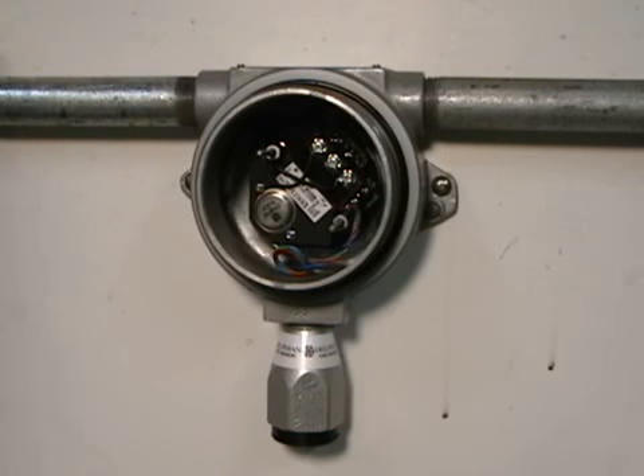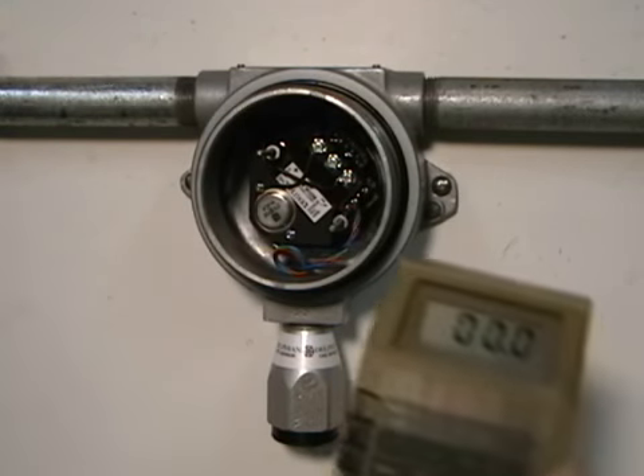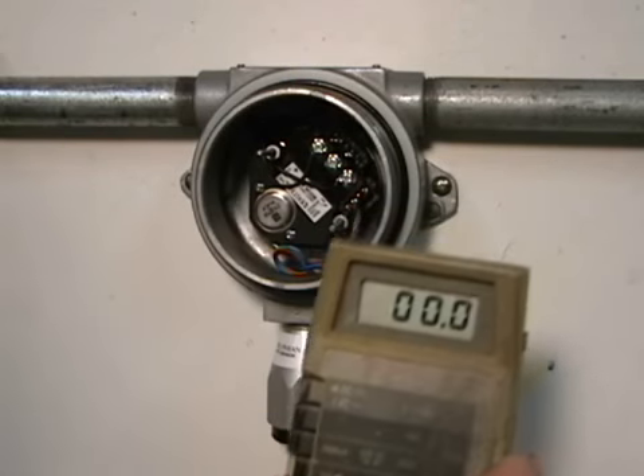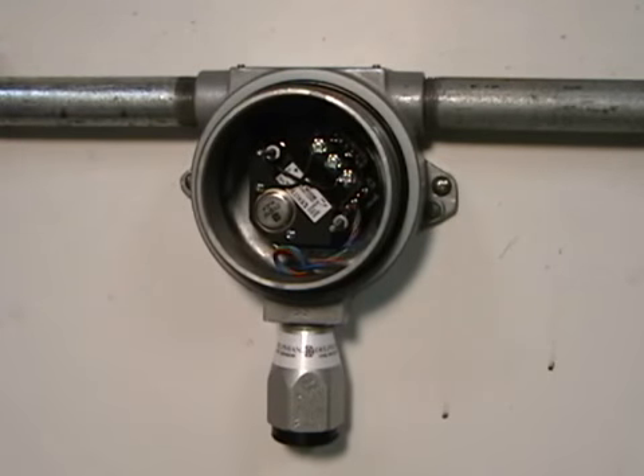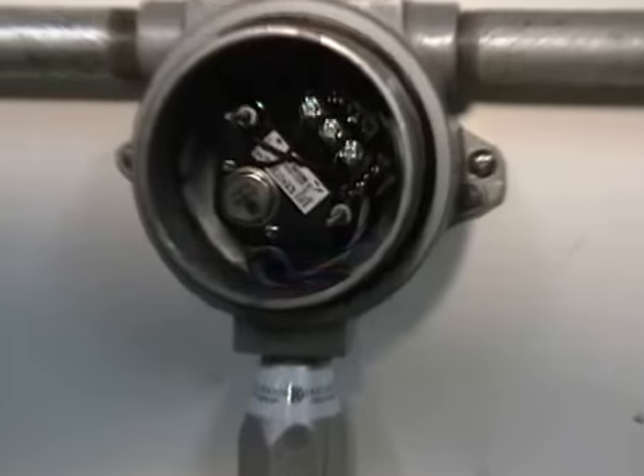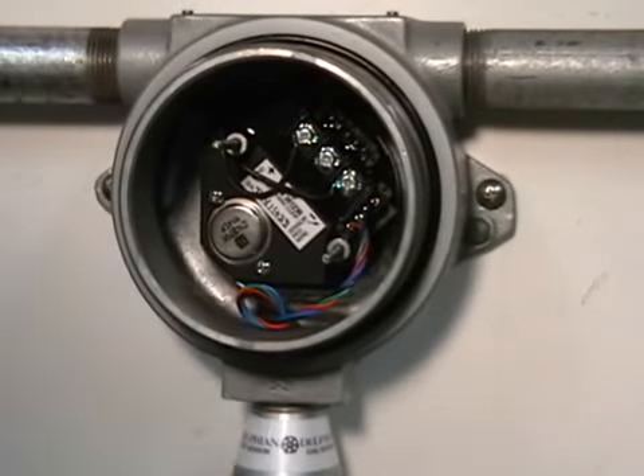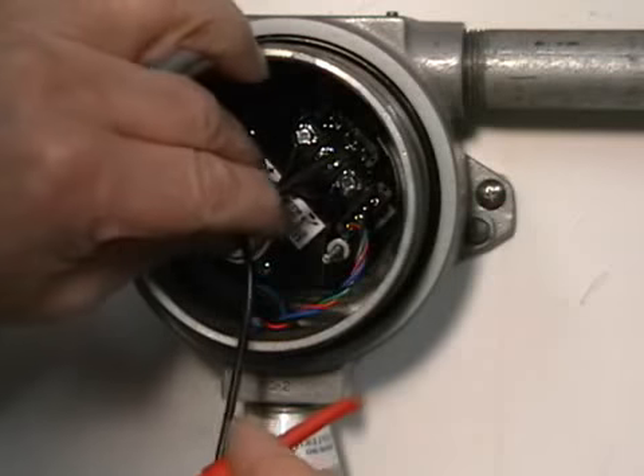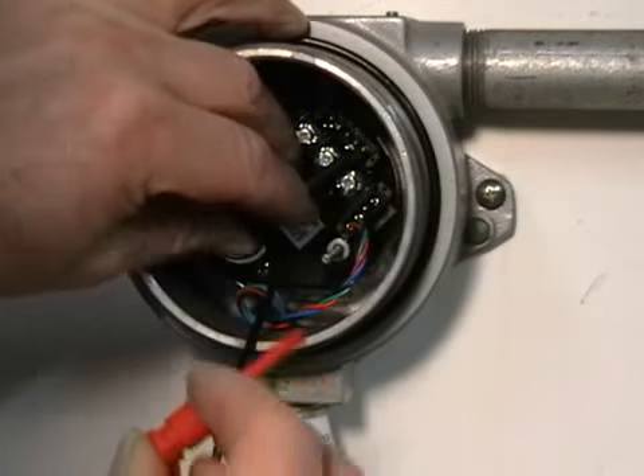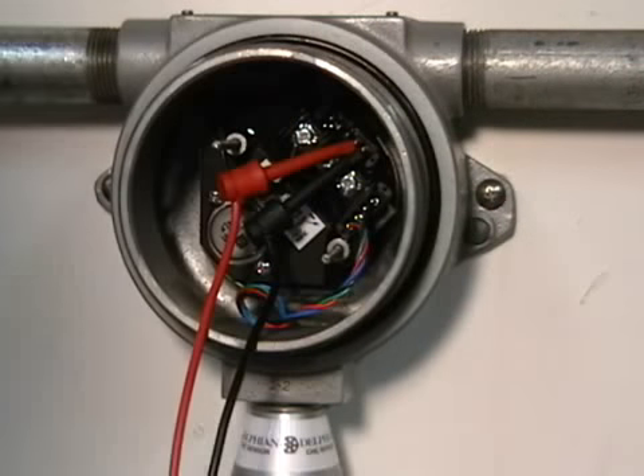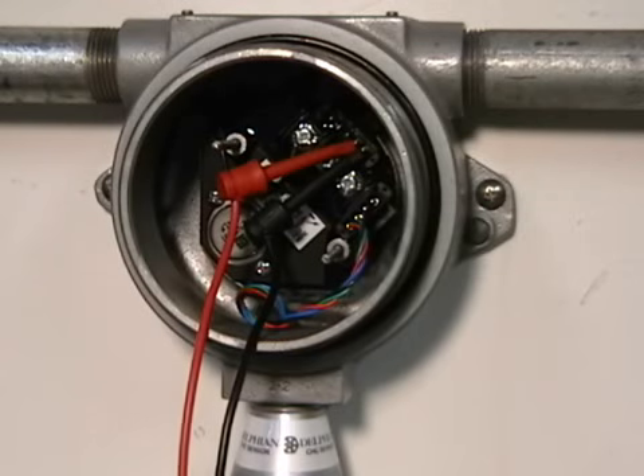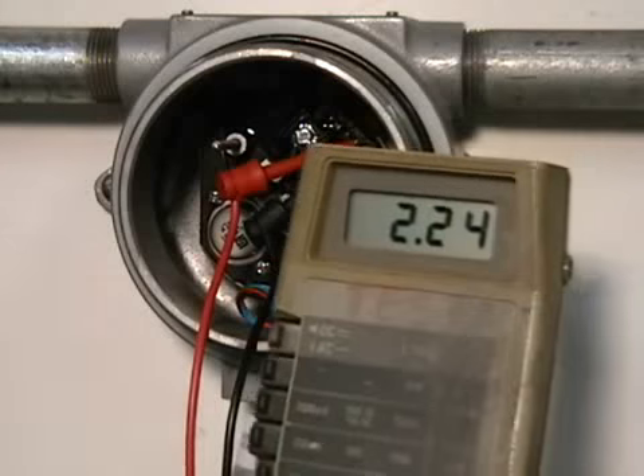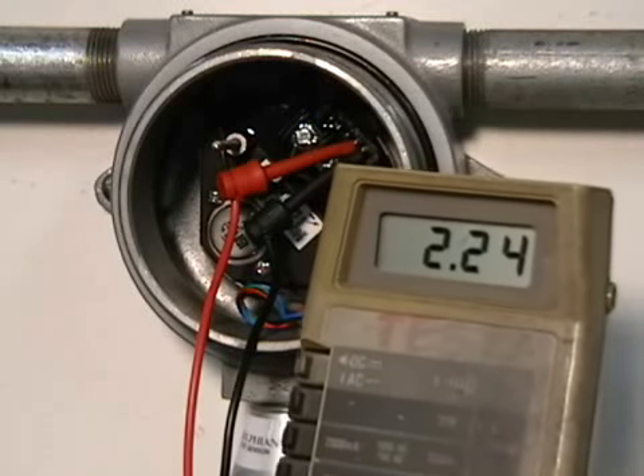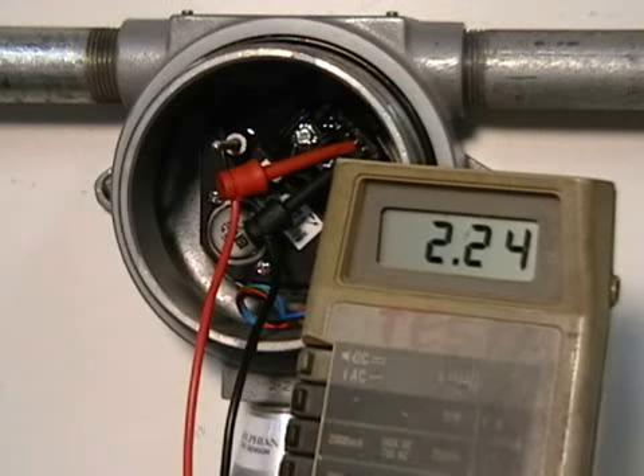You will need any standard DVM capable of reading ohms, milliamps, and voltage. Place the meter on the milliamp scale and connect the black probe to pin 5 of the 5-pin transmitter header and the red probe to pin 4. If the sensor is mechanically okay and the transmitter is working, the meter should display a milliamp output between 1 and 7 milliamps, although we would typically expect to see the value between 2 and 5 milliamps.